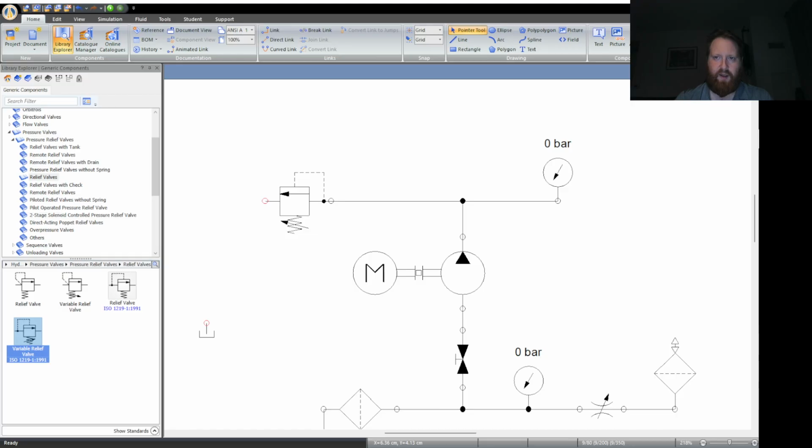And FYI, this is going to be where our output is connected to. Whatever we're connecting in our series, this is going to be going to our little divider that has our pressurized and our tank inlets. So we're going to put that in over there. And remember, this is the piece that you pull down and you rotate to adjust the amount of pressure, and we're turning this one to 500 psi before we start testing our system.